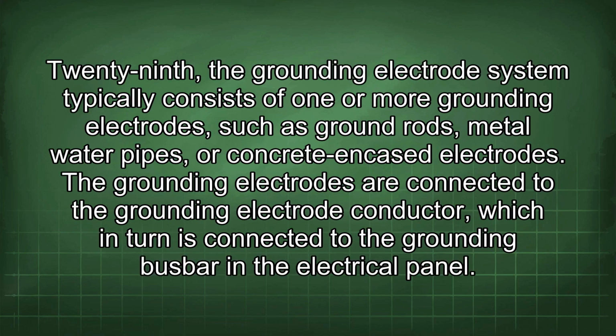29th. The grounding electrode system typically consists of one or more grounding electrodes, such as ground rods, metal water pipes, or concrete encased electrodes. The grounding electrodes are connected to the grounding electrode conductor, which in turn is connected to the grounding busbar in the electrical panel.